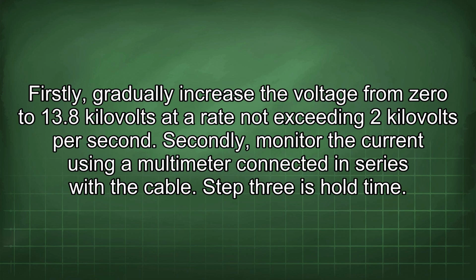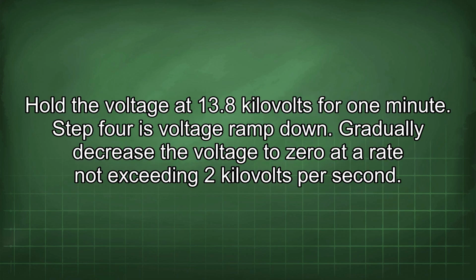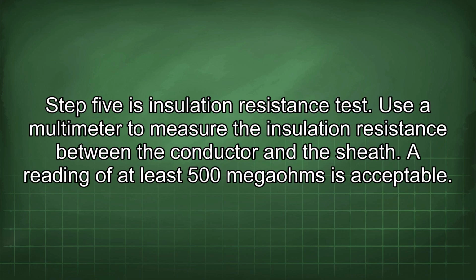Step 3 is hold time. Hold the voltage at 13.8 kV for 1 minute. Step 4 is voltage ramp down. Gradually decrease the voltage to 0 at a rate not exceeding 2 kV per second. Step 5 is insulation resistance test. Use a multimeter to measure the insulation resistance between the conductor and the sheath. A reading of at least 500 megohms is acceptable.